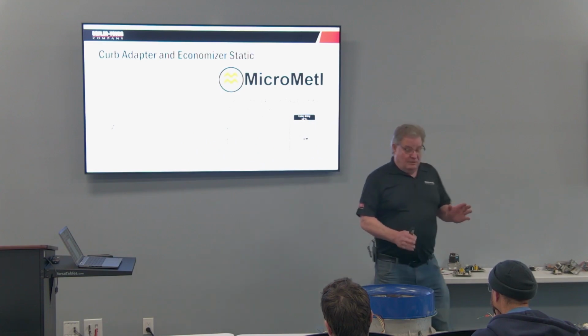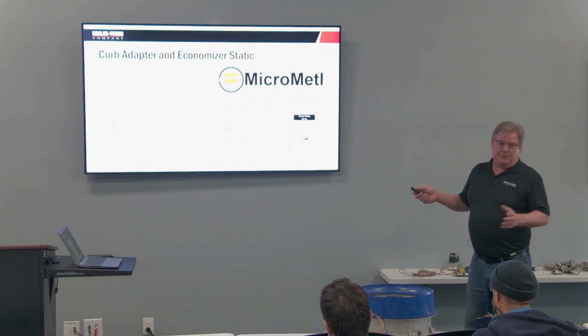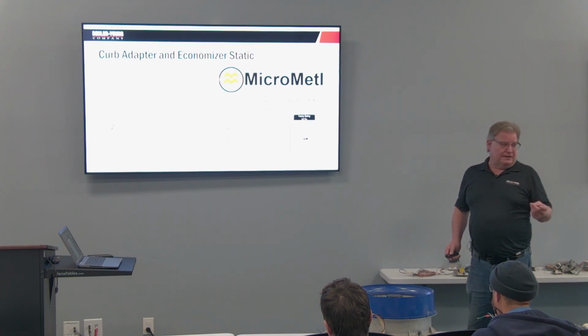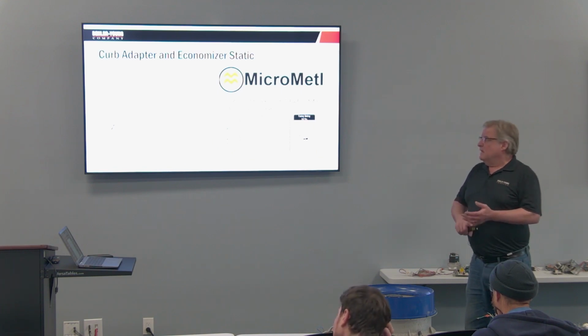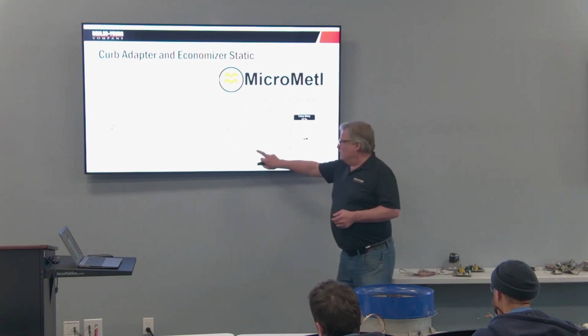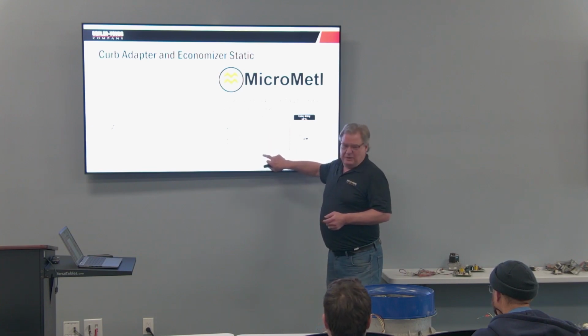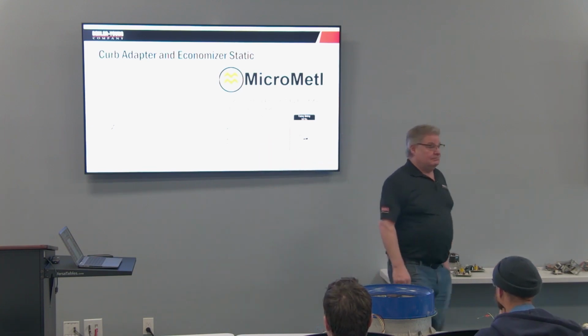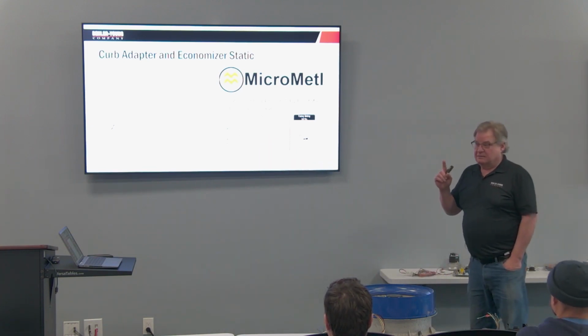Okay, so in my example we're looking at, I had 0.9 inches of statics. Everybody see how I did it? Pretty simple. I have an economizer. I'm going to just go with this number here and says, well, it says add 0.1. So I have 1 inch of static. That's my total.